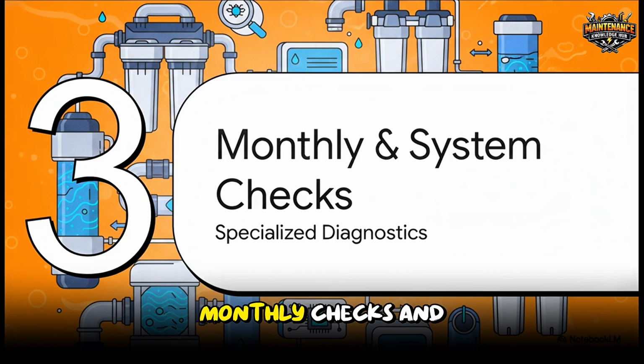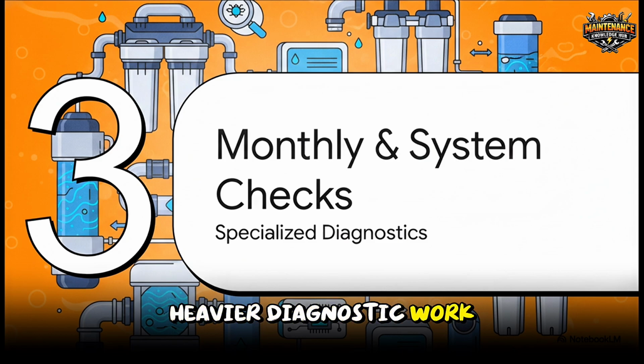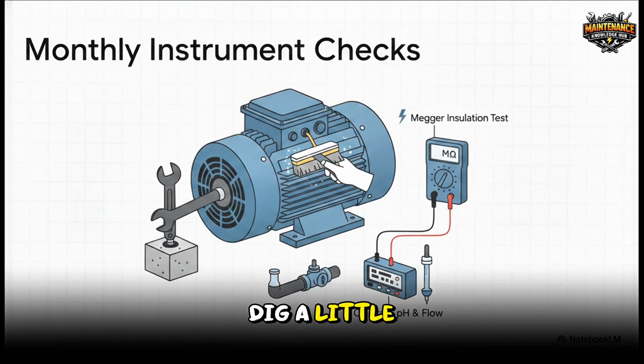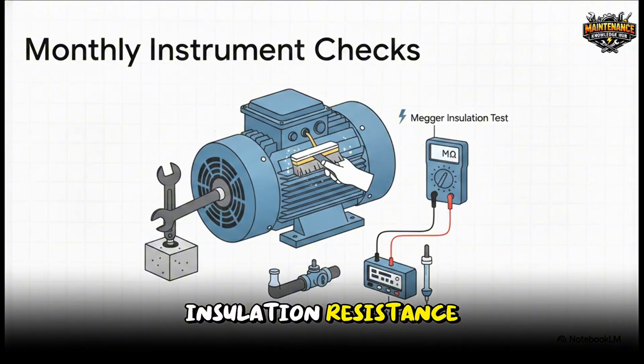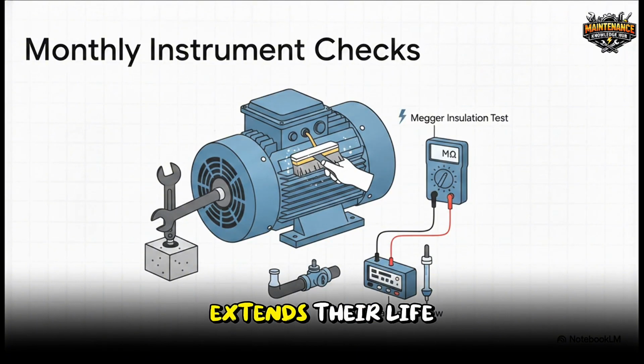Section 3, Monthly Checks and Specialized Systems. Moving up our preventative pyramid, we transition into heavier diagnostic work. Once a month, you've got to dig a little deeper. For your pumps, we're talking coupling alignments and making sure foundation bolts haven't literally vibrated loose. For motors, doing a Megger test to measure insulation resistance and cleaning out those cooling fins extends their life dramatically. And crucial point here, full calibrations on your pH analyzers, conductivity meters, and flow meters. If your instruments are drifting, your plant is drifting, right? You need those digital readouts to reflect reality.